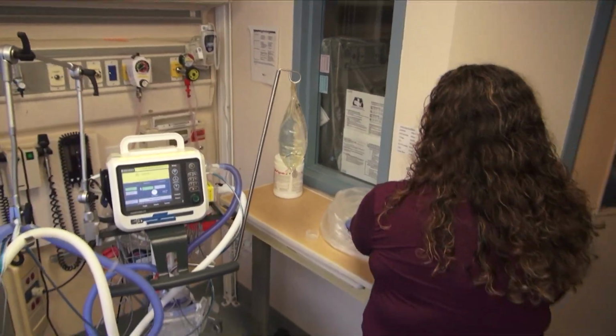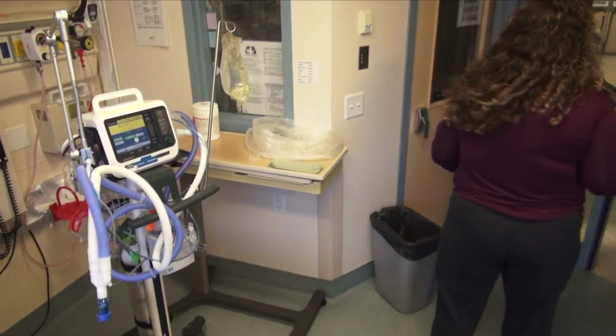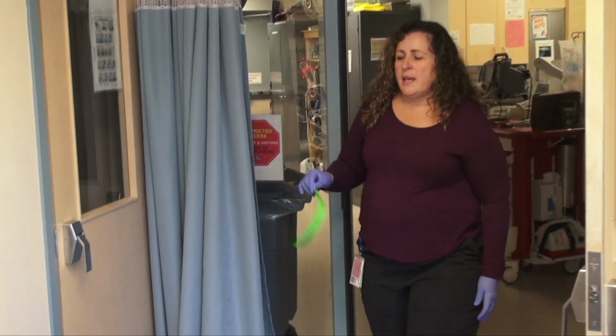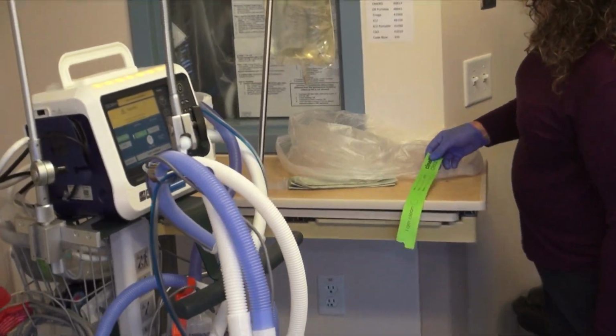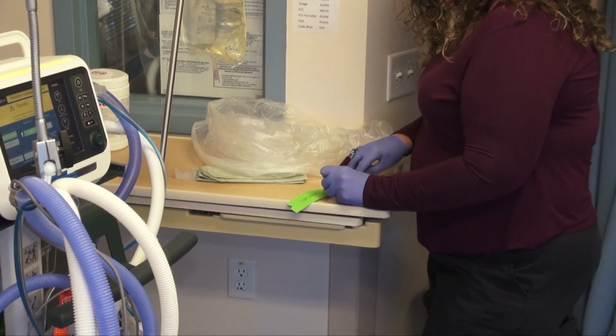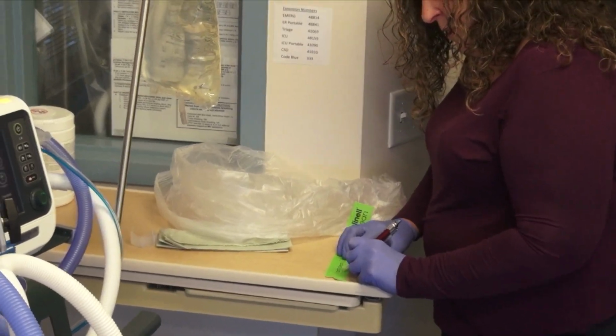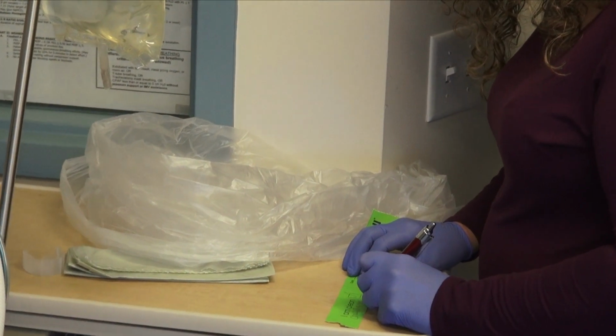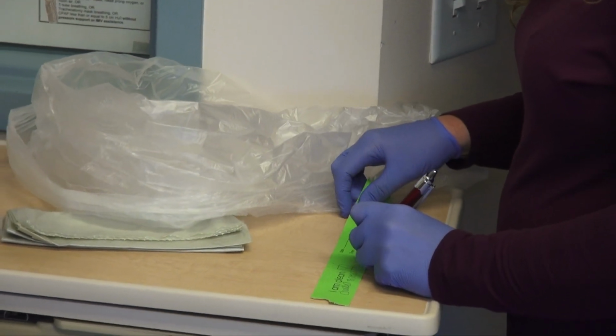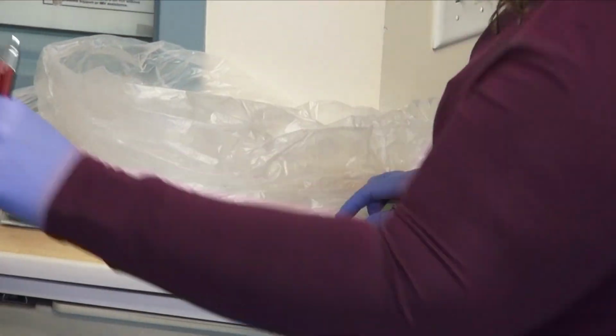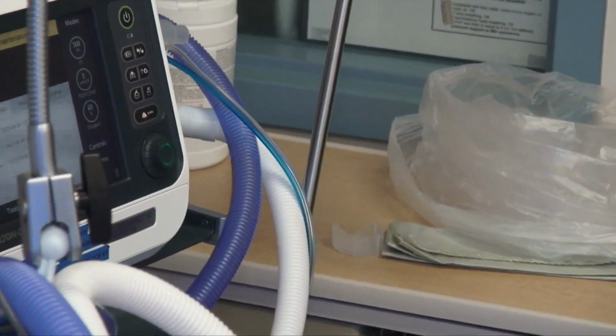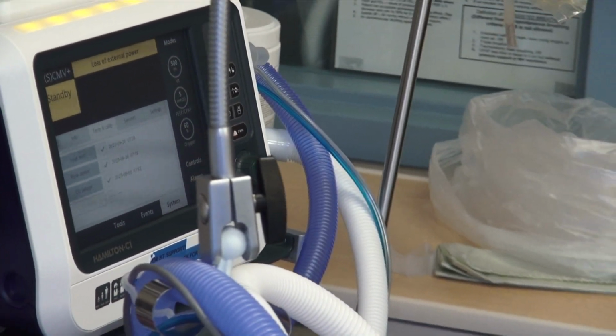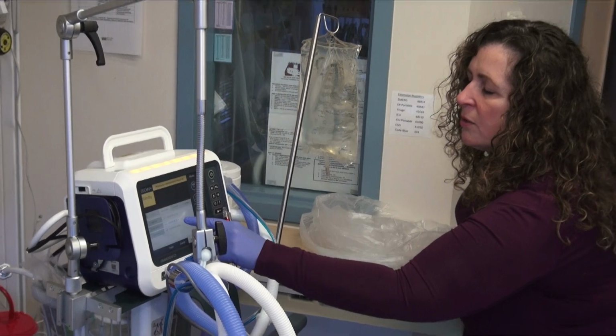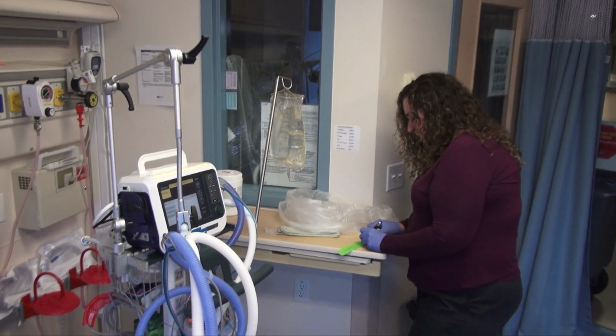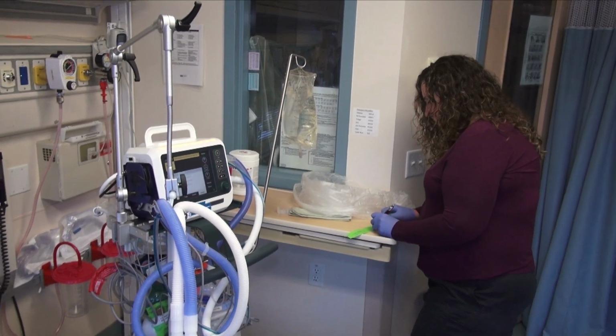The last things you're going to do is, in the bag, there is a bag to cover the ventilator, and I'm going to grab a piece of green tape where we're going to mark it that it's cleaned, checked, and ready to use. And you're going to put the date on it, that it matches this one here, 20th of September 23, and the time that you did the check, so 7:38 a.m. And then just put your name to it.